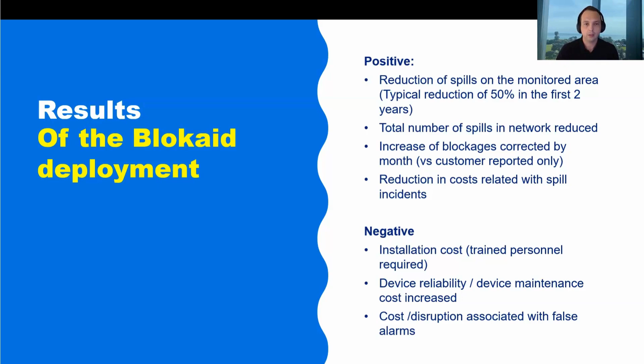There was also the cost and disruption caused by false alarms - some devices didn't behave as expected and reported false alarms. Since we were monitoring remotely, we couldn't tell if an alarm was false or real, so we still needed to deploy crews to the site, which meant extra cost we didn't want to incur. Finally, there's the cost associated with having an intrinsic safety certified device and maintaining that compliance, which was a very costly exercise for us as a water corporation.